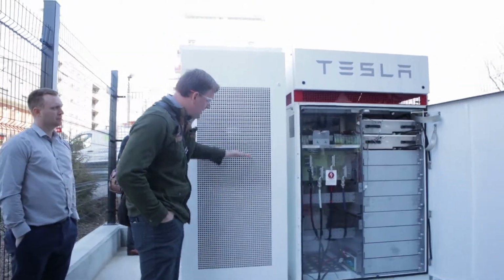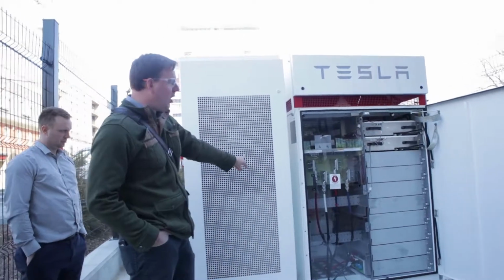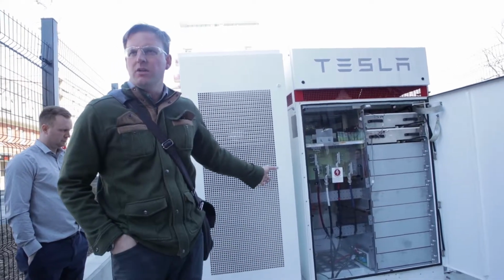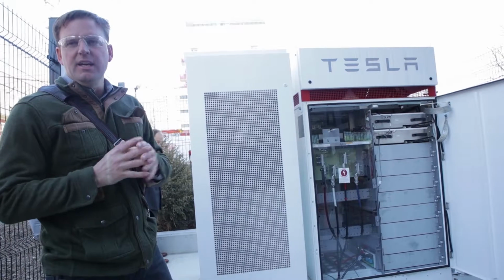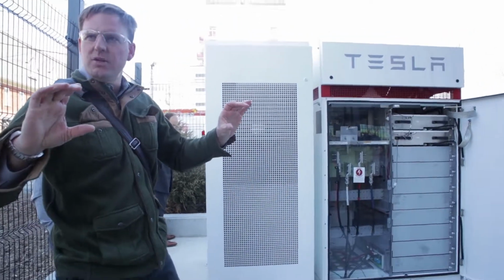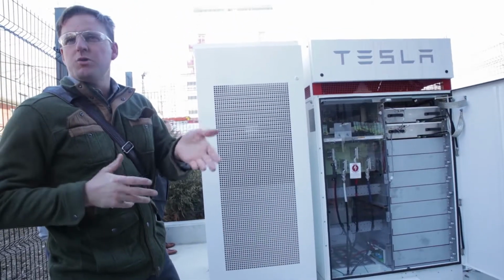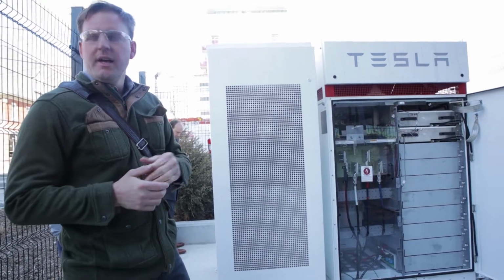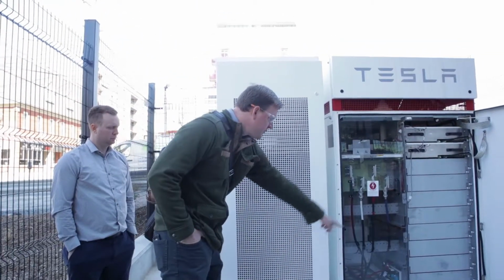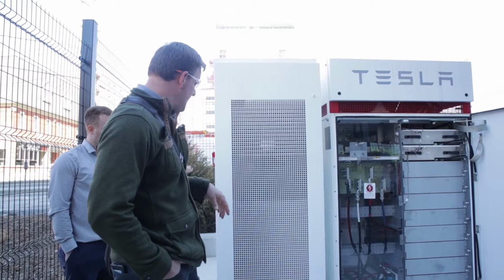There will be several stacks of them right here that go in, and they'll all be interconnected. It's a very special system in that each pod has a DC-DC converter which switches the 50 volts up to about 800 volts DC, and then goes on a common bus bar that traverses back over the inverter section.